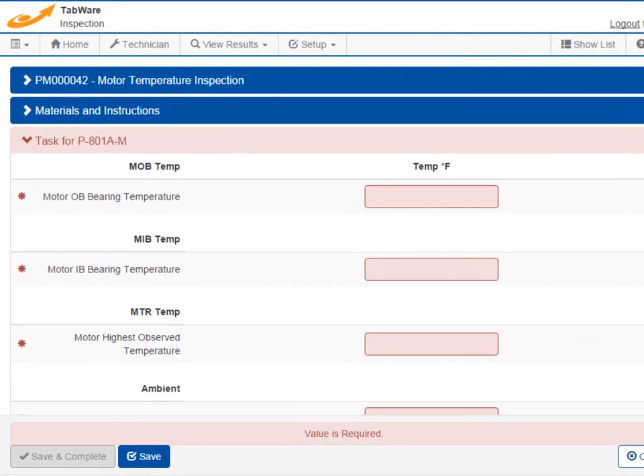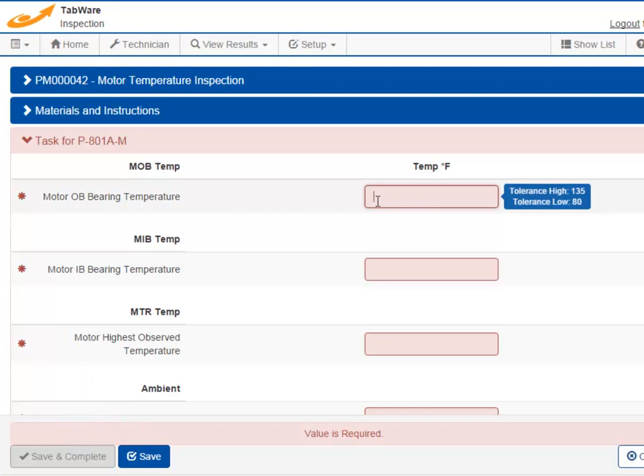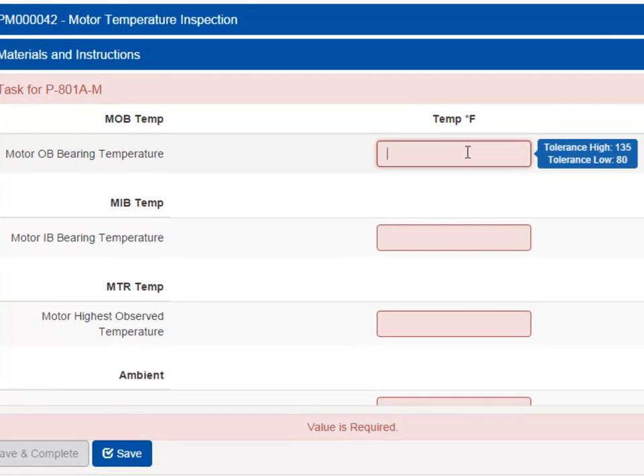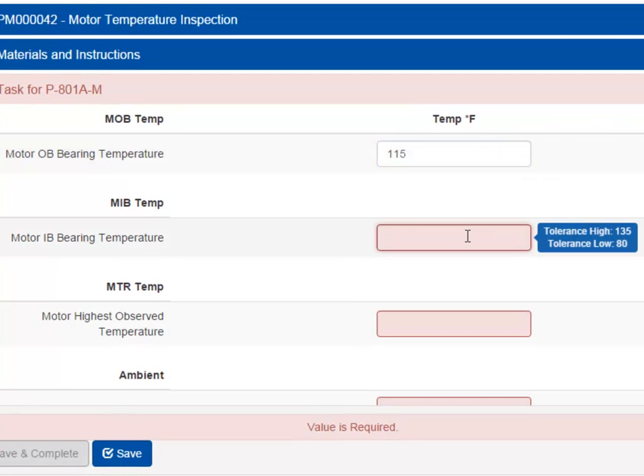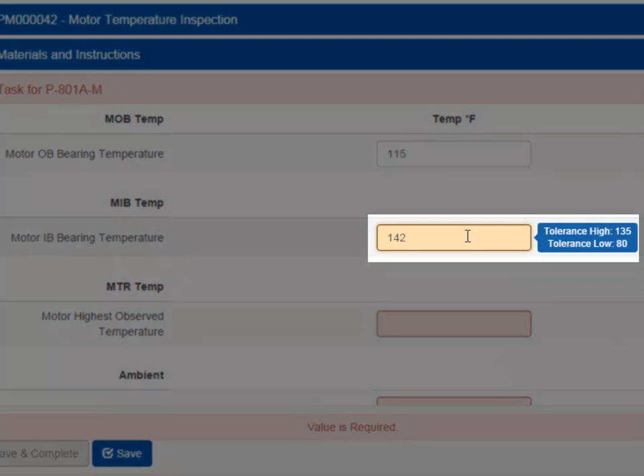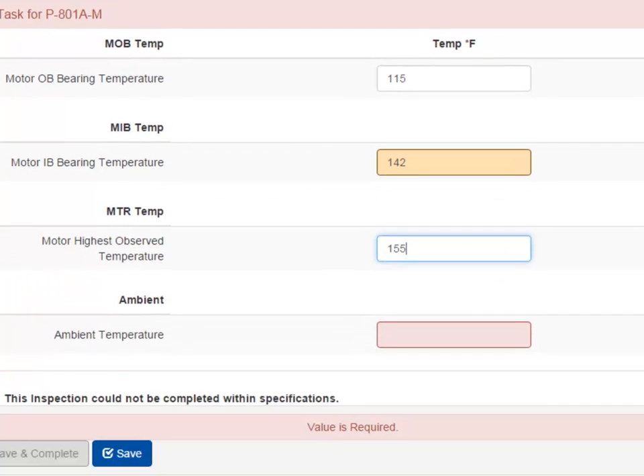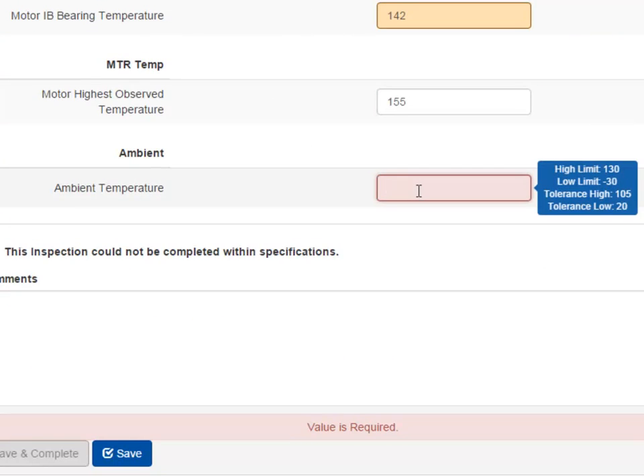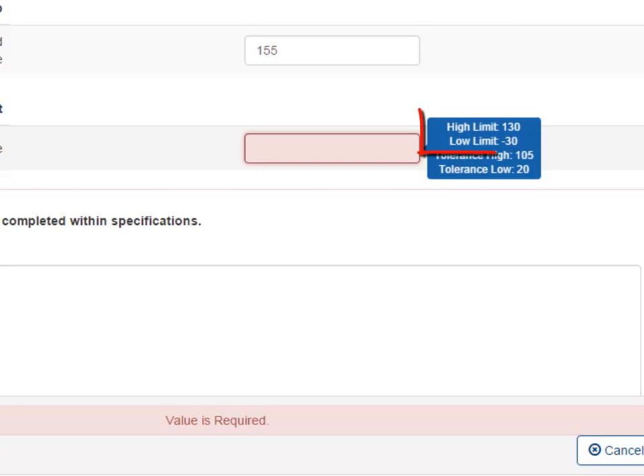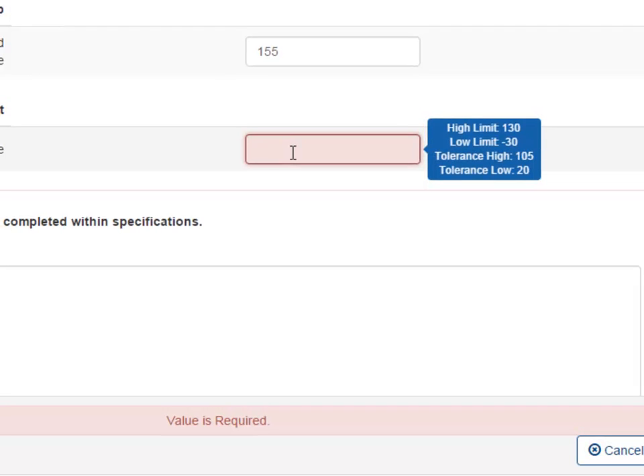Required fields are highlighted red. While we can save an inspection without completing it, we cannot complete it without populating all required entries. For bearing temperature, we have determined acceptable upper and lower tolerances. If a value falls outside of that range, the value is flagged as a failed condition. In addition to upper and lower tolerances, a field can be forced to only accept valid numeric entries by specifying limits. Limits can prevent inspectors from entering invalid readings.